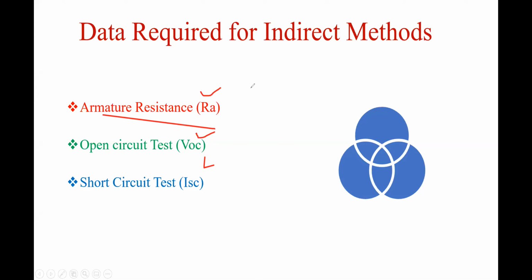In this case I use the voltmeter ammeter technique, because armature resistance is in the category of medium resistance. That's why I choose the voltmeter ammeter technique. First of all, I calculate the DC resistance, that is RDC, across each two phases, between R and Y, Y and B, and then R and B, and then I take the average. Then I apply the skin effect, because on the armature winding a sinusoidal flux is present.